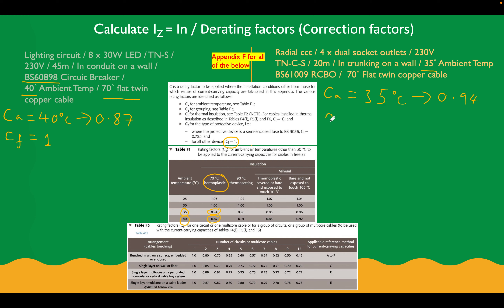For CF: we're not using a BS3036 fuse here — we're using a 61009 — so CF is going to equal 1. We're not including the grouping factor CG in this example, but it's worth being aware of. The ambient temperature table is table F1, and the grouping factor table is table F3 — just flip to those pages in the on-site guide.